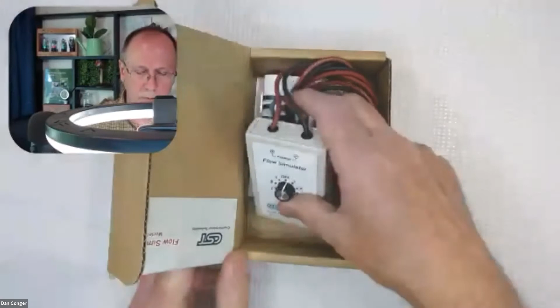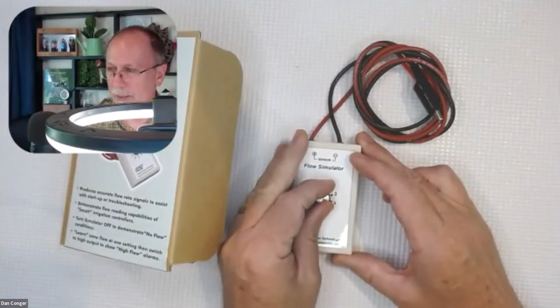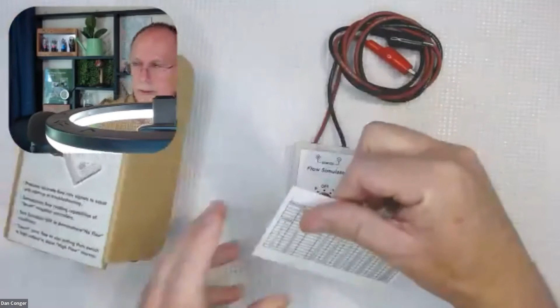So my experiment was, which is more accurate for measuring it? This reads 0 to 5 psi. This reads 0 to 150 psi. Which one is more accurate? I'll cut to the chase on that one. Turns out this is slightly more accurate because this is a tighter range, but it didn't matter in feet of water. It really didn't make that big a difference. The biggest difference, the reason to use one over the other, is how you're going to mount it. This is intended to thread into a fitting, and this one is intended to drop into a tank.